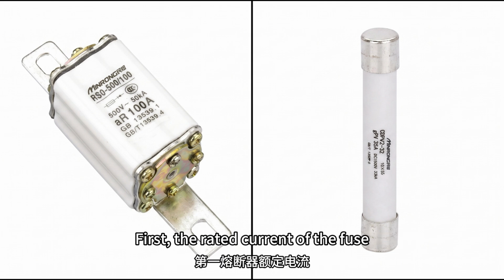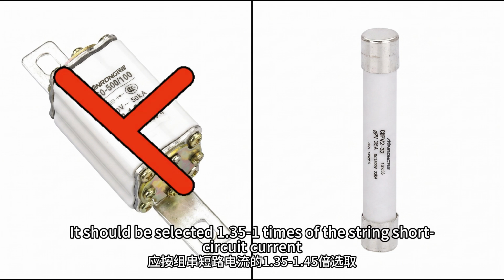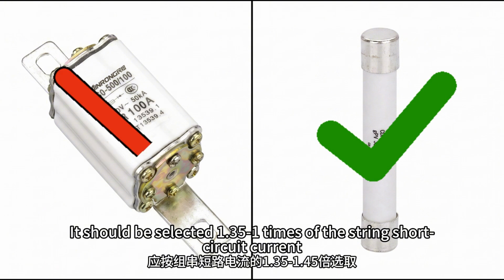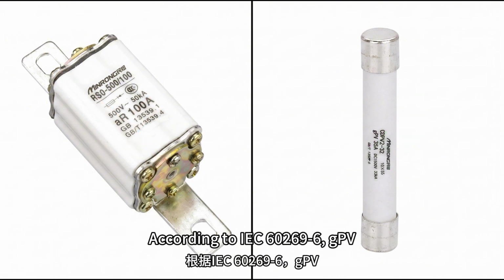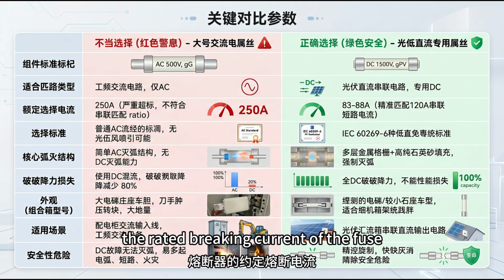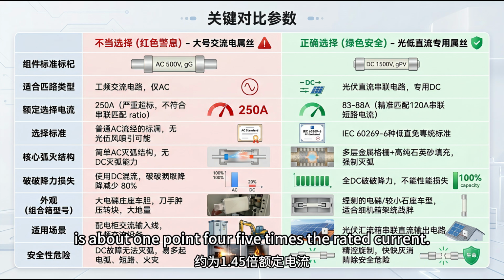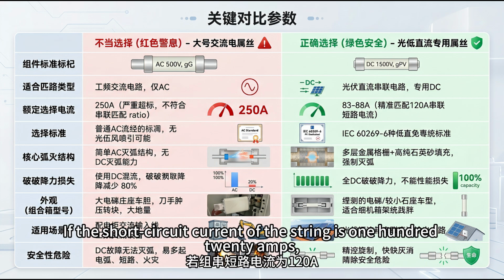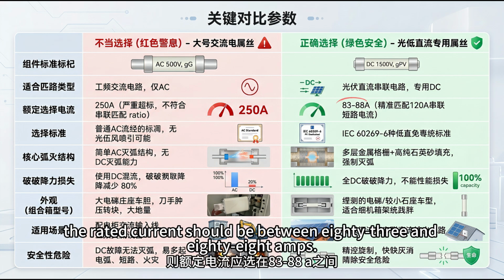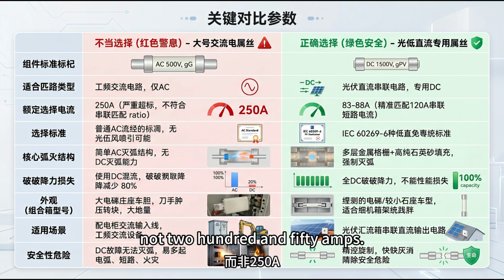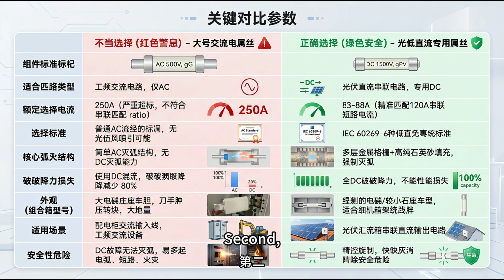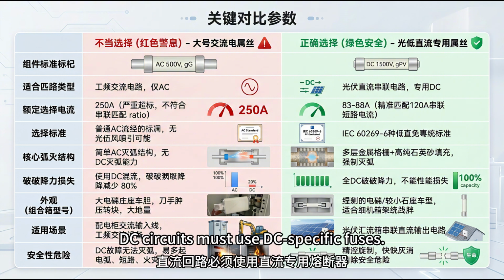First, the rated current of the fuse. It should be selected at 1.35 to 1.45 times the string short circuit current. According to IEC 60269-6 GPV, the rated current should be between 83 and 88 amps, which is about 1.45 times the rated current. If the short circuit current of the string is 120 amps, the rated breaking current of the fuse should not be 250 amps.